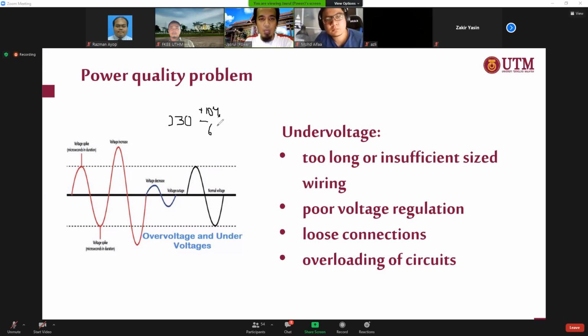We have a range of plus 10% and minus 6%. So we have 230 plus 10% minus 6%. As long as the voltage is within this range, it's actually good power quality. But when we talk about under voltage, we're talking about a voltage value lower than minus 6%, and it has happened for around 1 minute — there's a time frame. If the duration is longer than 1 minute, we declare it as an under voltage condition.